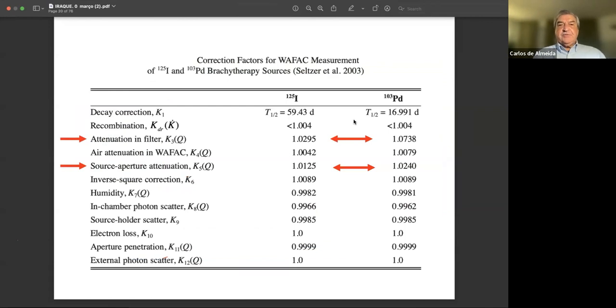The major corrections that you have to take into account are the attenuation of a filter that's placed to absorb some of the low energy that you're not interested in on the clinical side, which is in the order of 2%, and the source aperture attenuation, also in the order of 1.25%. The rest of the corrections are quite small, almost close to 1. But to handle this particular chamber requires a lot of time, a lot of effort, and a very skilled staff to do that. Next one.